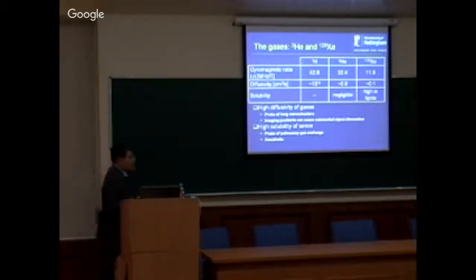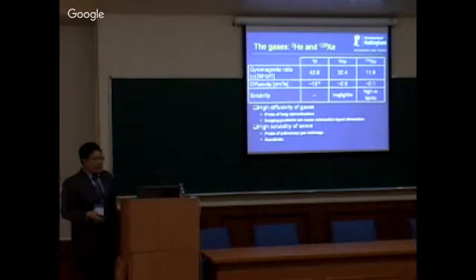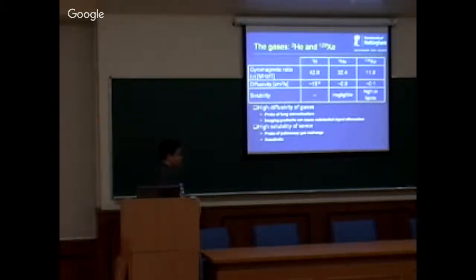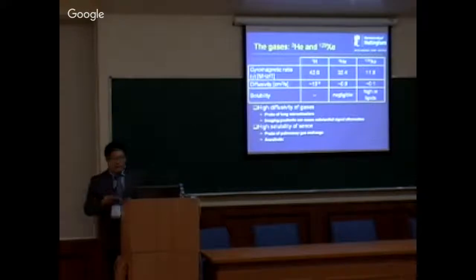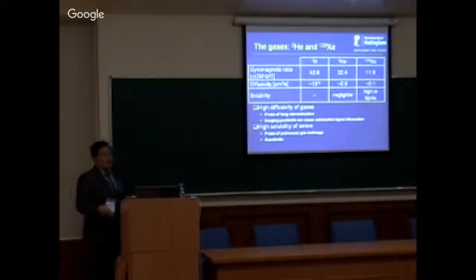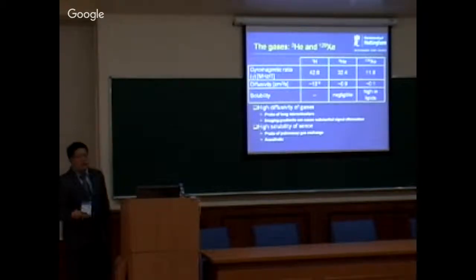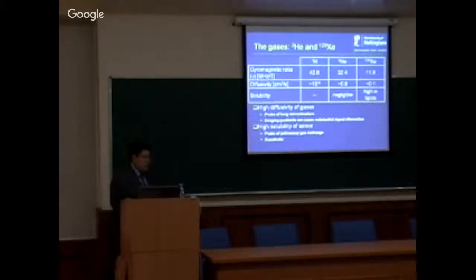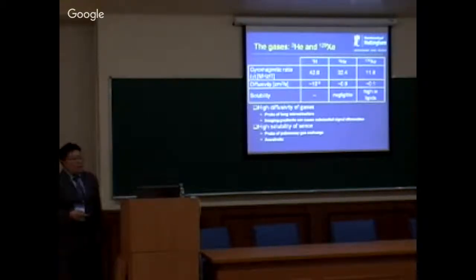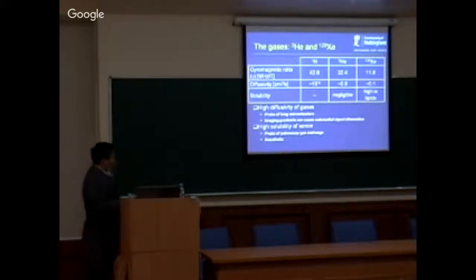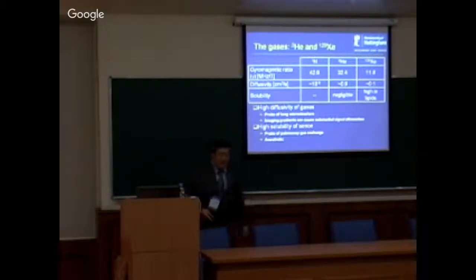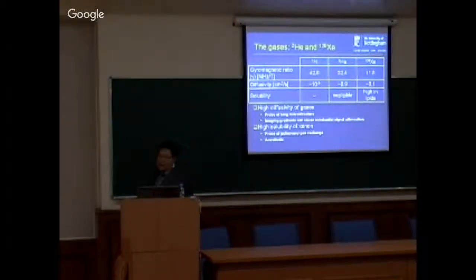But here I only talk about 2 gases. Thomas mentioned this morning the third gas, krypton, but I didn't do any krypton. For helium and xenon, to really use this technique, you still need some special modifications to your scanner. You can see the gyromagnetic ratio is different, so you need a new RF amplifier and a new RF coil. Also, we need a new pulse sequence. You need to notice the gas diffuses really fast, so you need to design your pulse sequence carefully. But there are some good things. Because the gas diffuses really fast, it can be used to measure the lung structures.